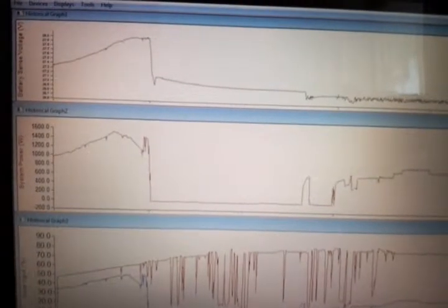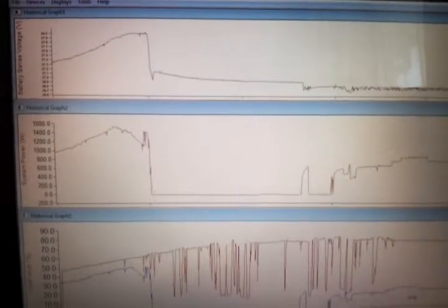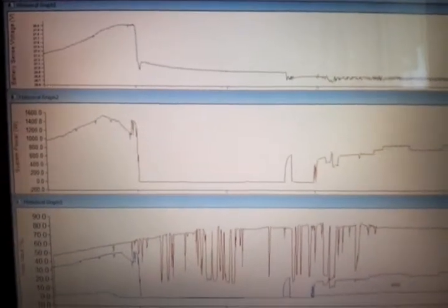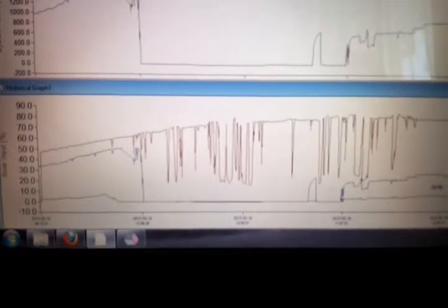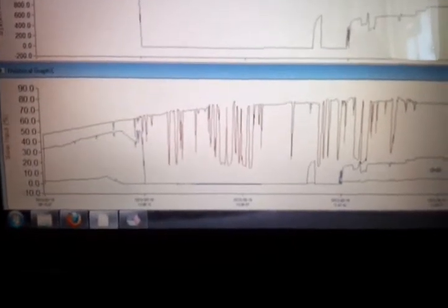On the top, we have the battery voltage, and then in the middle, we have the power in watts that was delivered by the chargers. And then along the bottom, we have a more complicated trace that shows in red the available strength of sunlight as a percentage from a sensor on the roof that estimates available power. And then the blue trace is the charge current from the 60 amp charger, and the bottom green trace is the charge current from the 15 amp charger.